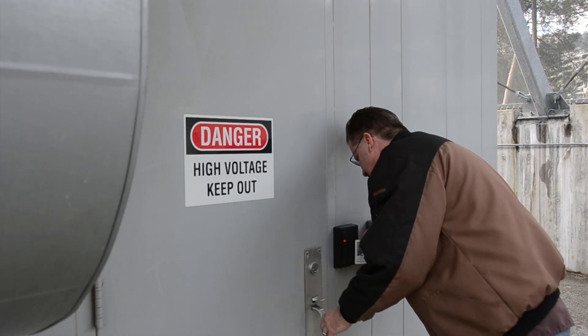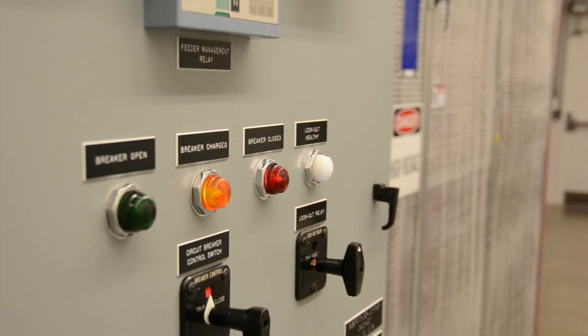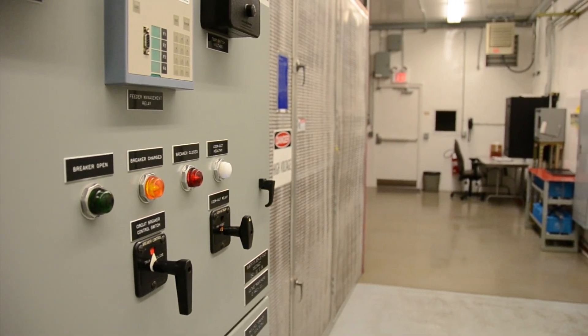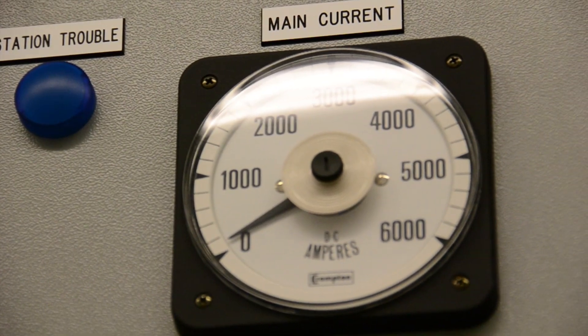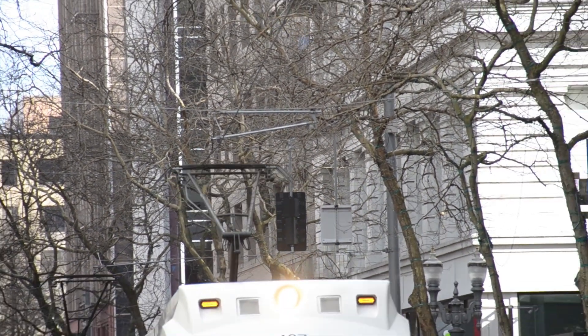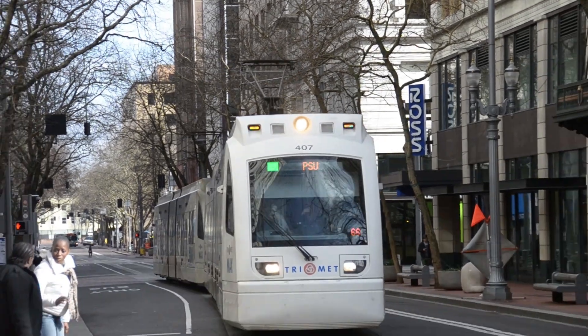Power supplied by Portland General Electric and PacifiCorp to the MAX substations, spaced approximately one mile apart along each light rail route. Substations take the incoming power at approximately 12,000 volts of alternating current and rectify it to 750 volts direct current to power the overhead line, which delivers power to the trains.